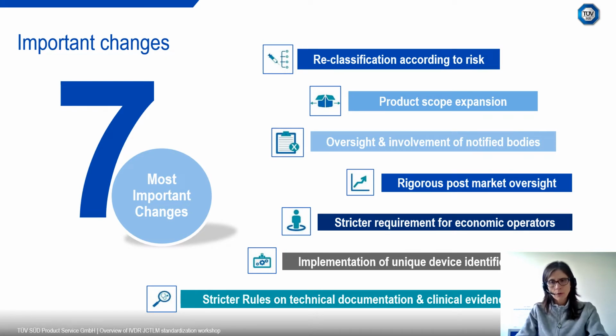Also made stricter are requirements for economic operators. The directive really focuses on the responsibility of the manufacturer. This is maintained in the regulation with a really detailed description of what the requirements are for manufacturers, but there are also new economic operators, such as the distributor, that are not named in the directive. They, of course, already exist, but their responsibilities are not defined in the directive, but they are defined in the regulation.